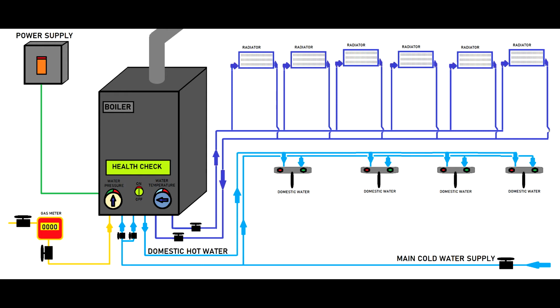If everything is okay, the printed circuit board will initiate the pump that will circulate the heating agent. The flow switch will send information to the printed circuit board telling it that the circulation is okay. Then the boiler will start to heat and the radiators will start to get hot. This is a system which provides instant hot water on demand, but this is not a commercial system, so you do not have a ring circuit for the hot water. You have to wait a little bit until the hot water reaches the tap from the boiler. But anyway, this is an instant hot water boiler.